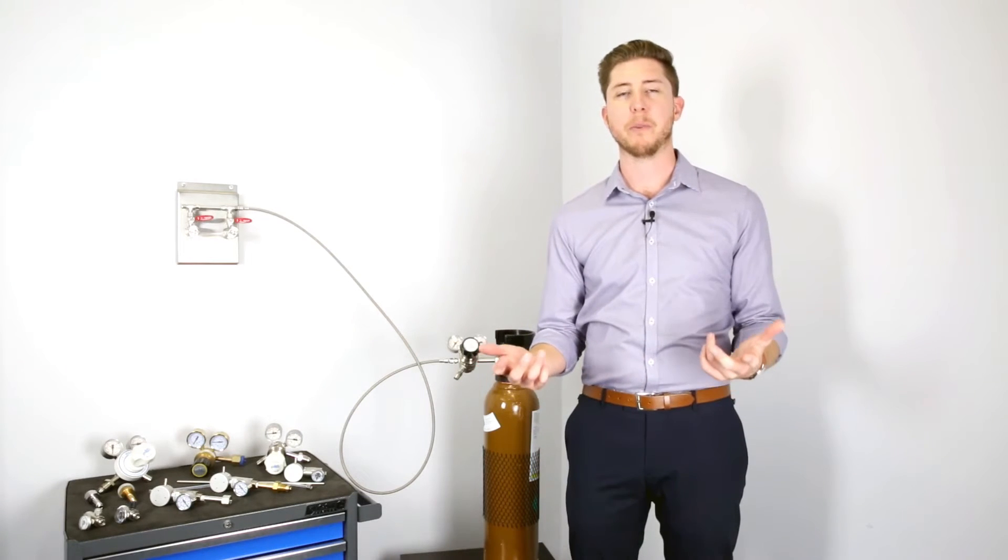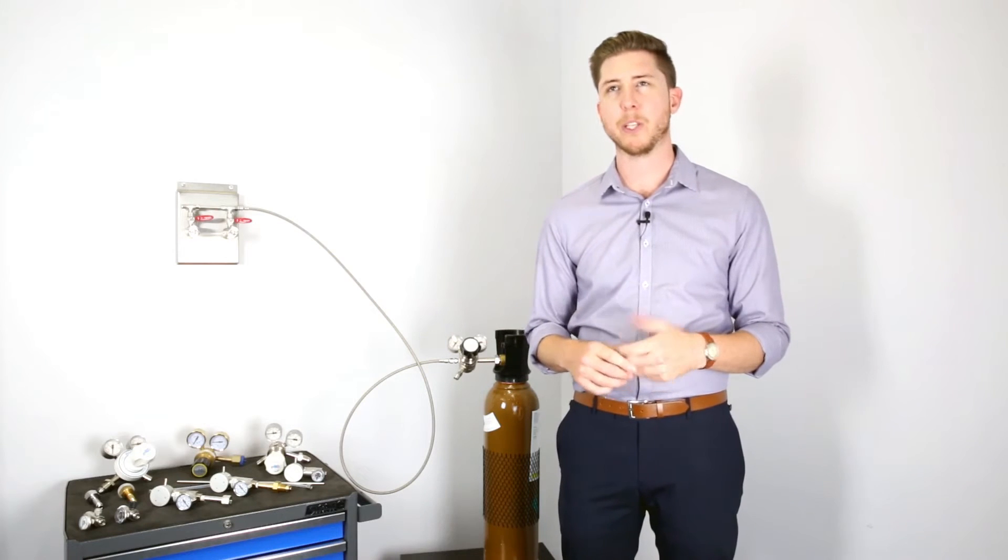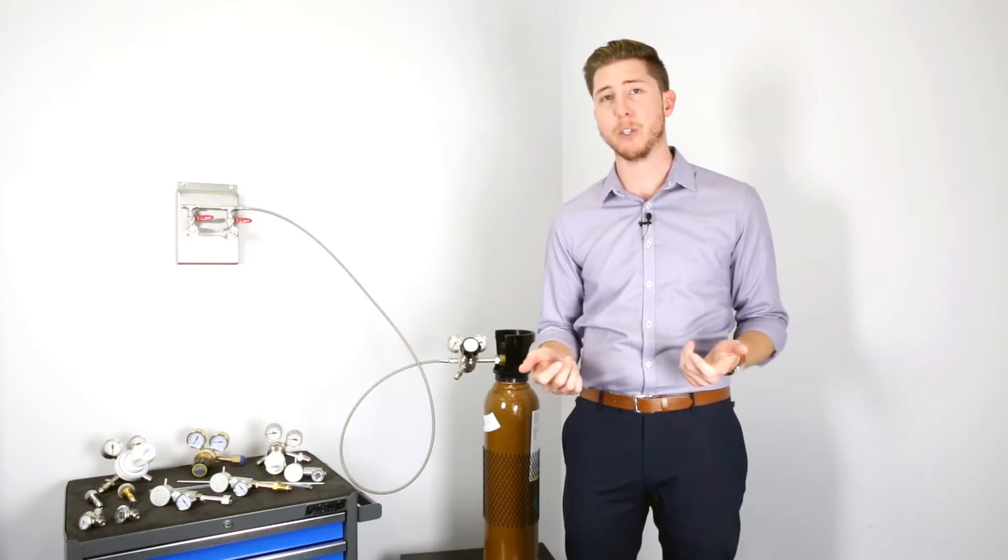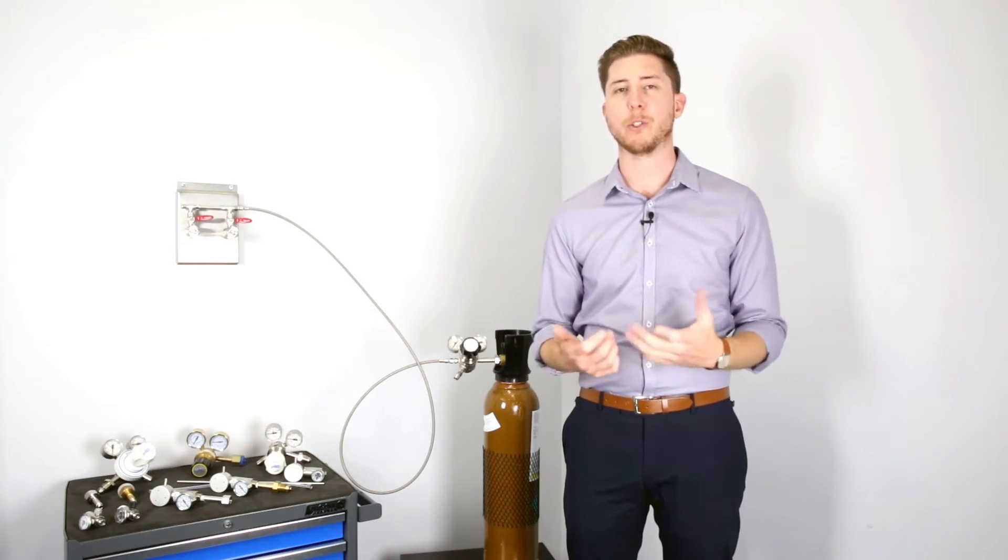The key decision making criteria for materials is whether or not the gases are corrosive or non-corrosive. This will determine whether or not we use stainless steel, nickel-plated brass or brass for our regulators and hardware, and whether or not we use Teflon or Tygon tubing.